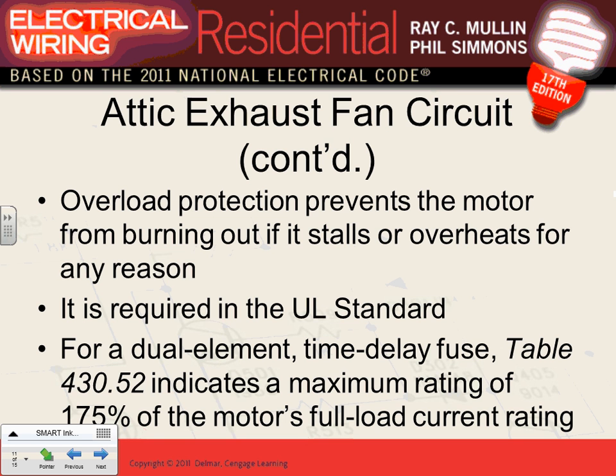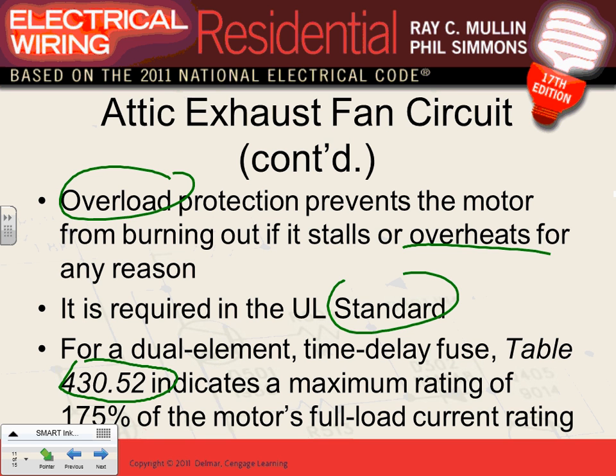So we need an overload, guys. This will have a built-in overload on it to protect it from overheating and burning. These are all by UL standard, as we know. And when we size overcurrent protection devices, this is what we went over last week. We were sizing like any other motor, guys.